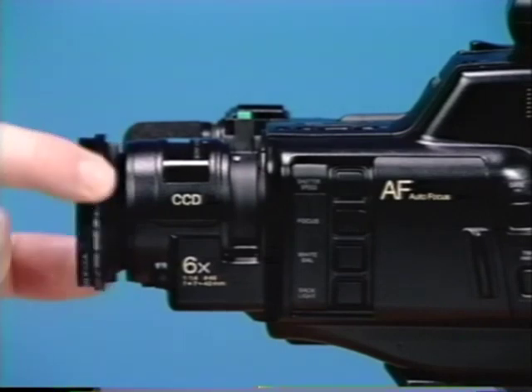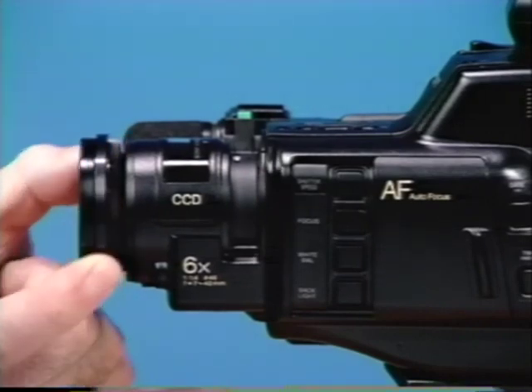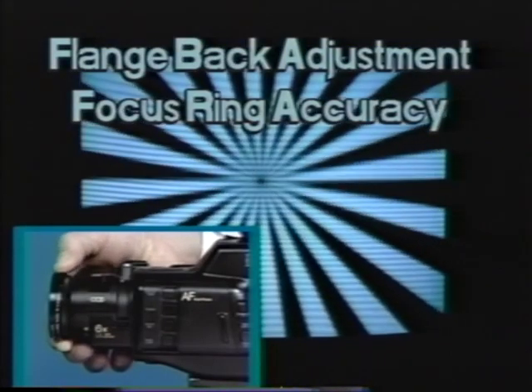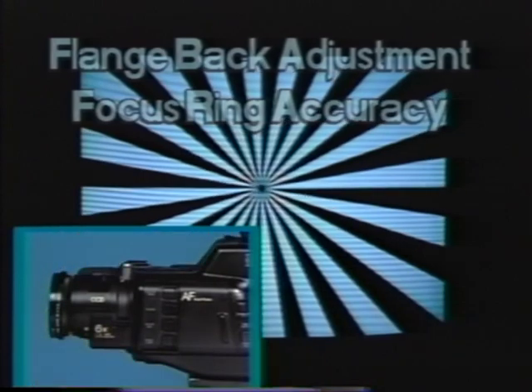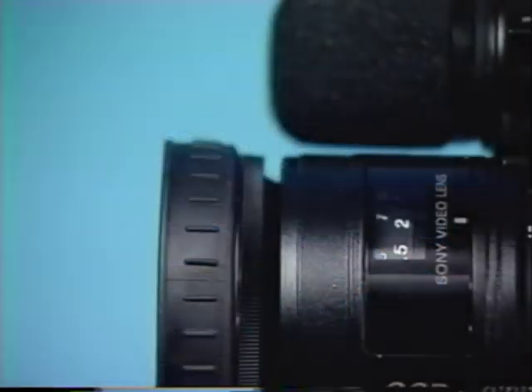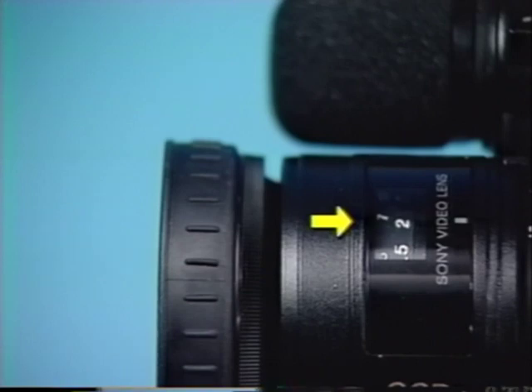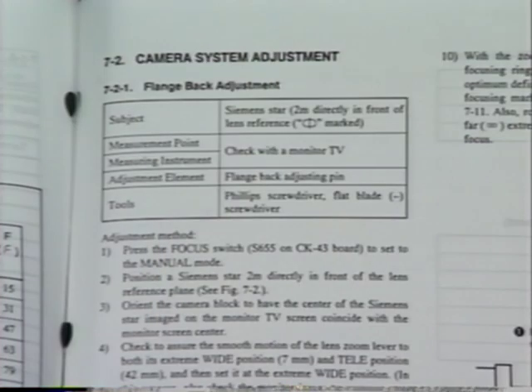When automatic focus is disabled, you should be able to position the lens manually. Manually rotate the focusing ring for maximum definition at the center of the Siemens star pattern. Confirm that the focus mark on the lens is at the 2-meter scale mark within 1/16 of an inch. This should be the same distance as the camera from the Siemens star pattern. If it is not, then perform the flange back adjustment as described in the service manual and repeat the previous steps.